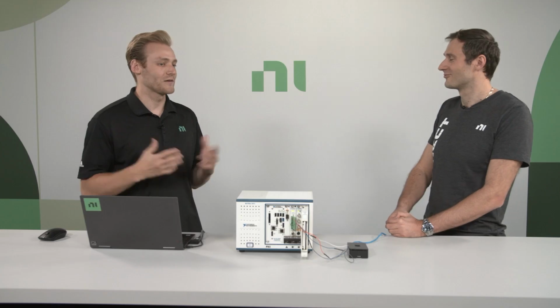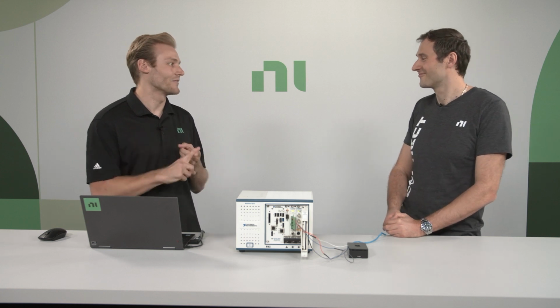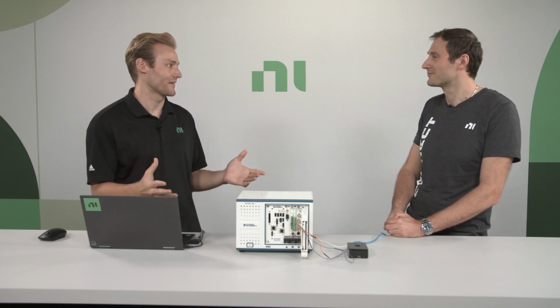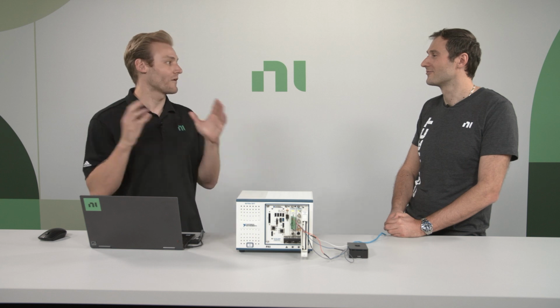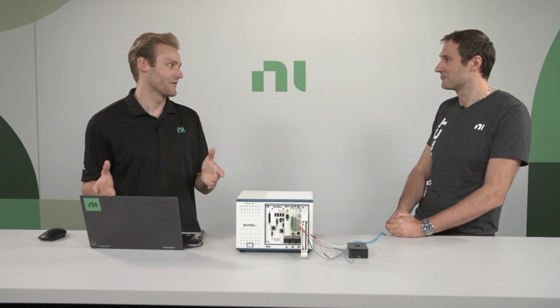So that's what it supports, but what it actually does is it is a software equivalent of the physical interface that you'd expect to have on a traditional box instrument. The need for this is based on the PXI form factor. Obviously, the modules are about this thin, so we didn't have the room to add in the buttons and knobs and screens and everything else like that. So instead, we built all of that functionality into InstrumentStudio.